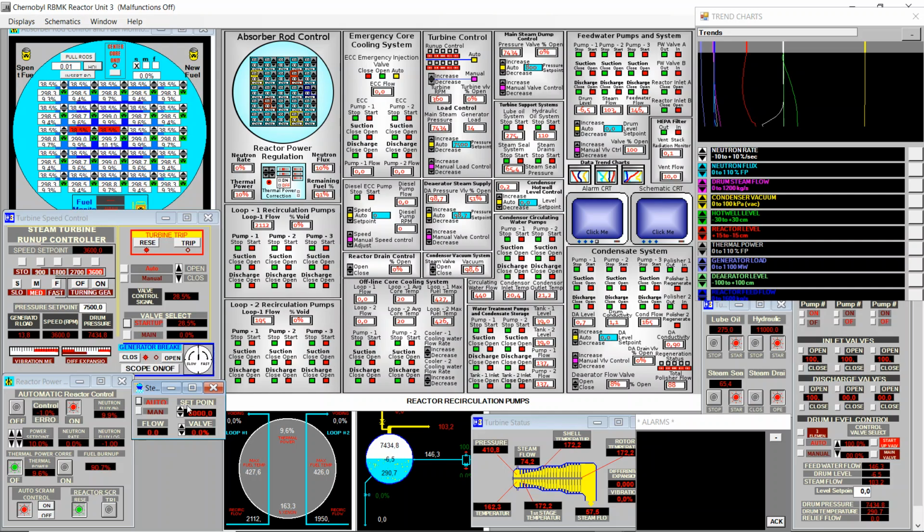So once I go off grid, we'll have a lot of power from the steam that we have to direct to another place. So this will go to the relief valve of the main steam dump control system. This will open the valve when the pressure goes above 8000. It makes no sense to put it higher because we will just go higher in pressure in the drum without any reason, because now we want to power down, so I think 8000 is a good number here.